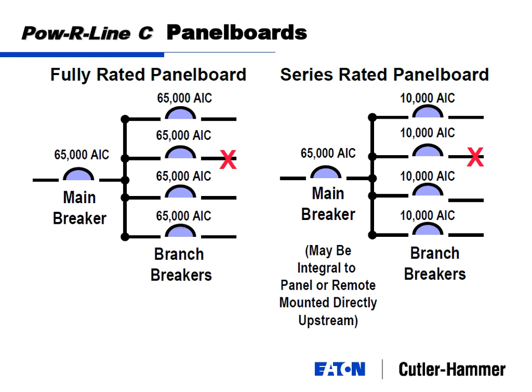And because you've got a head start on opening, you're not starting from ground zero at full 65,000 amps. Just because of alternating current, you start at zero and you work up and then you go down. Because of that, your contacts are going to have a head start and start opening. So that's why one of these two breakers, I'm not going to tell you which one, will trip, even though it's not rated for it.